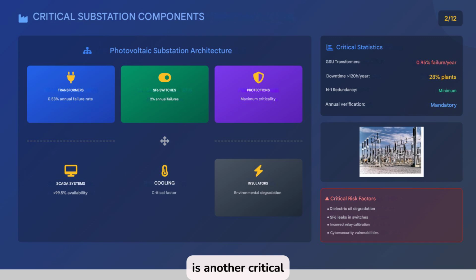Cooling is another critical aspect. If the system fails or does not adapt to the environment, the transformer's internal temperature increases, accelerating its degradation and reducing its lifespan. Insulators, exposed to aggressive environments, degrade over time, which can cause electrical shock or short circuits if not detected early. The lack of redundancy in many facilities means that a single failure can bring the entire plant to a standstill. Although there are regulations for annual inspections, compliance is uneven and often insufficient. In addition, there are cross-cutting risks such as dielectric oil degradation, SF6 leaks, calibration errors, or cyber attacks, which must be carefully managed.